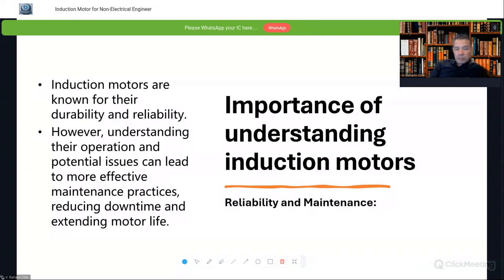By default, an induction motor is a robust machine, and knowing the components that make up the motors and how they interact with each other gives us a good understanding of where the potential issues may lie and how to effectively tackle them before they become a major problem. Most of the issues with motors are vibration and bearing failure, especially in sleeve bearing motors. We will look into it in detail after this. And then you need to carry out the maintenance program to ensure that the motor can run without any issues. So understanding the induction motor is important for the audience involved in the maintenance of the plant.